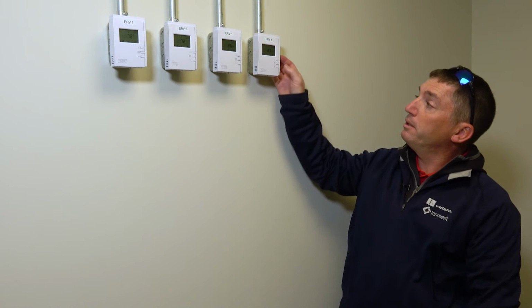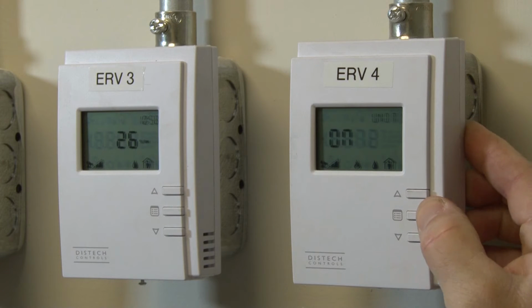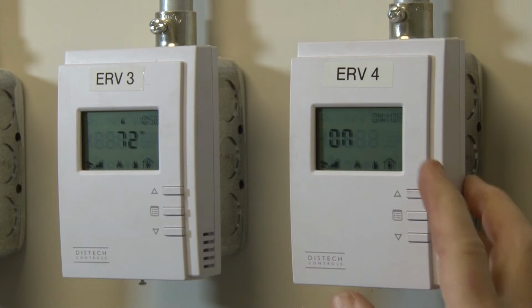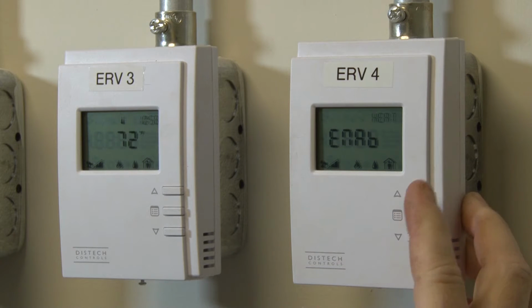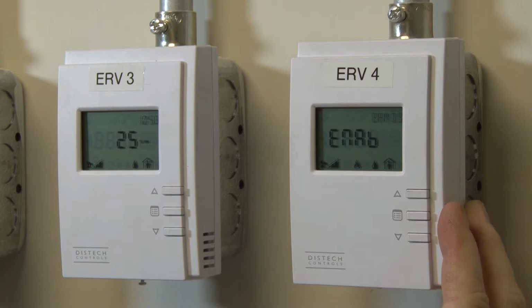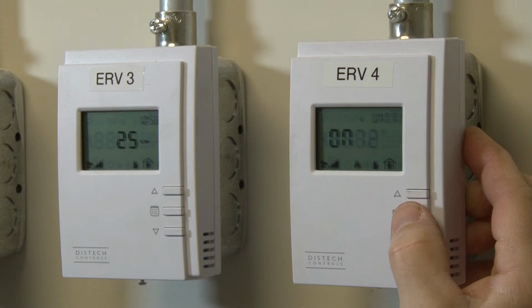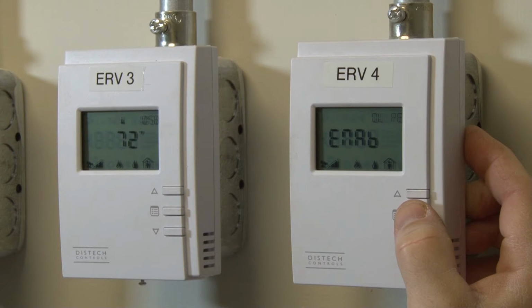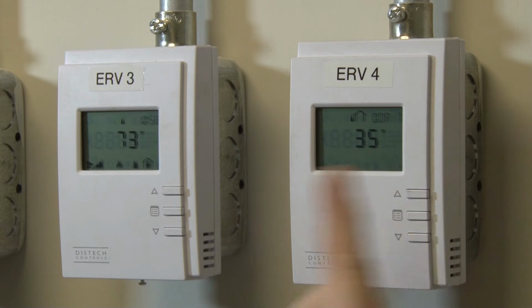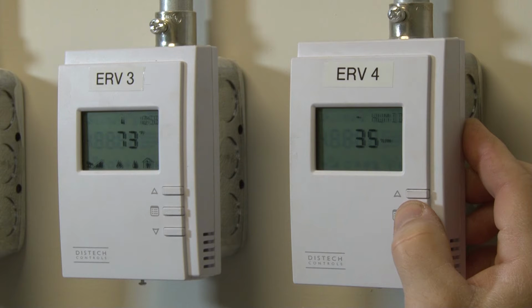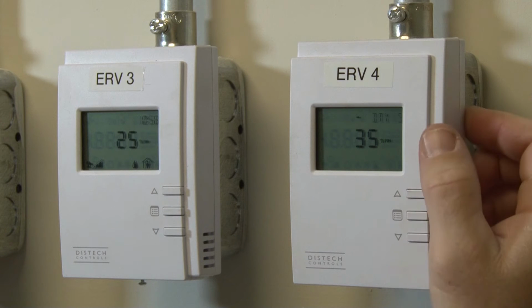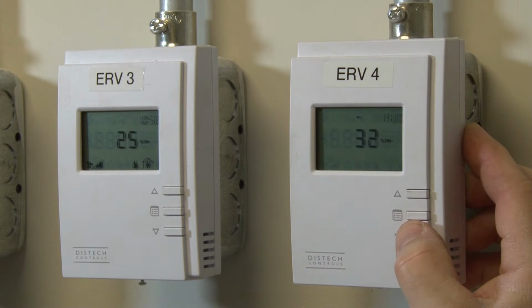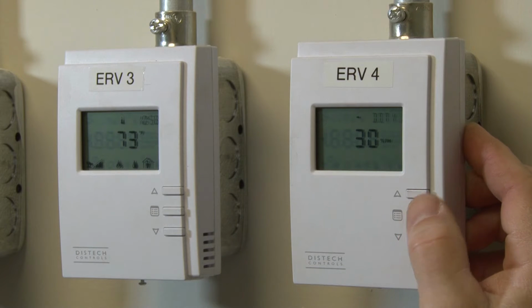Okay, so using the enter button, you can scroll through. Your first choice is going to be whether the unit is on or off. Second choice is going to be whether the gas furnace or heat is enabled. Third choice is cooling. Fourth is humidity. Fifth is the energy wheel. And then it'll show you the outdoor temperature, which is just a reading. And on ERVs 3 and 4, it's going to show you what your current relative humidity set point is.